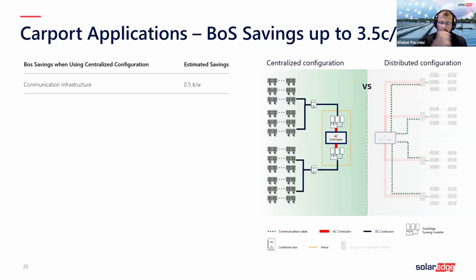First, you're saving by having a centralized configuration. You do not need to bring communication infrastructure - Ethernet or RS-485 cable, and not only cables but conduits - to the inverters located closer and distributed around the array. On average, that's a half a cent a watt savings.